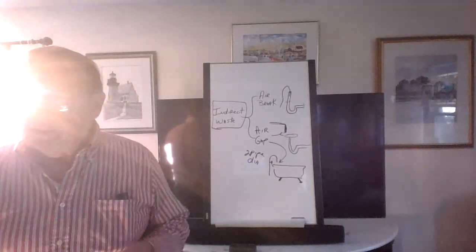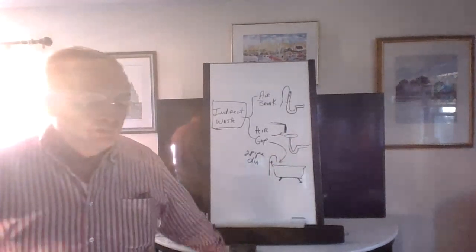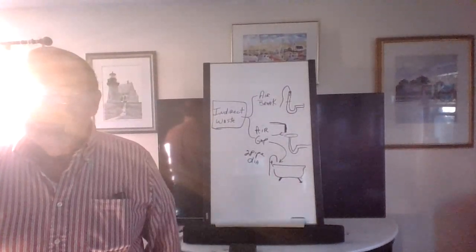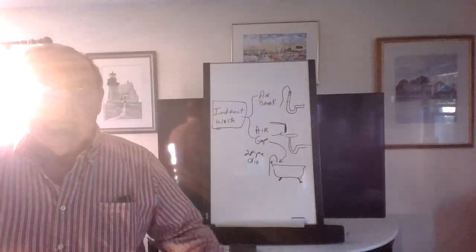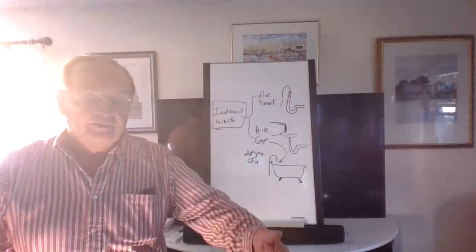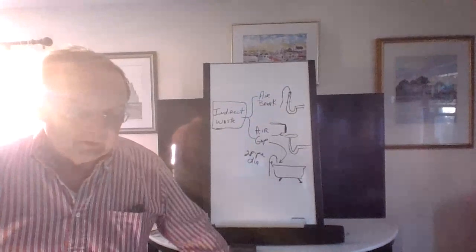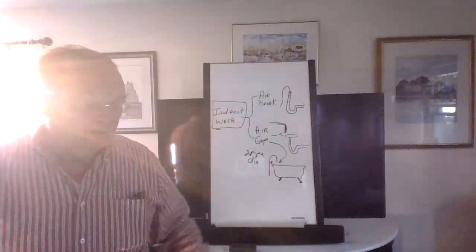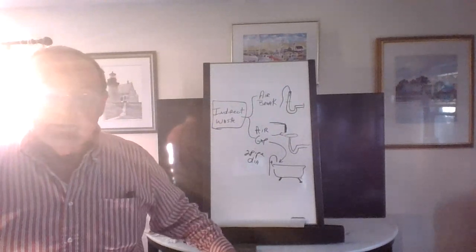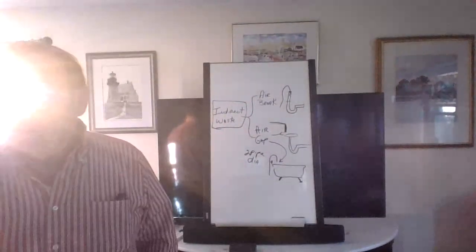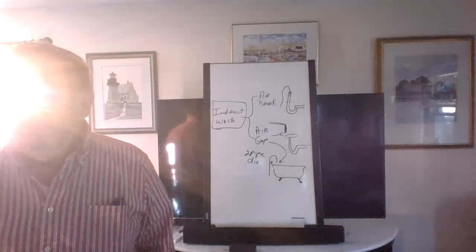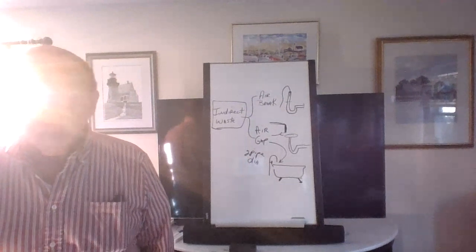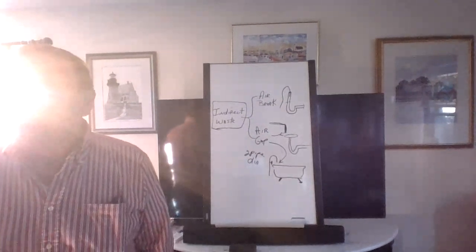So you guys that I didn't do this with, just picture a long 4-inch pipe in a building, we'll say a stadium, for example. You might have half a dozen or more water closets all lined up. Now, if they're floor mounted, not wall mounted, they can all Y into the same drain. Okay, that's a battery of fixtures, adjacent fixtures. They're all next to each other and they're similar. In this case, they're the same. Okay, that's a battery. So for this class, that's good enough.